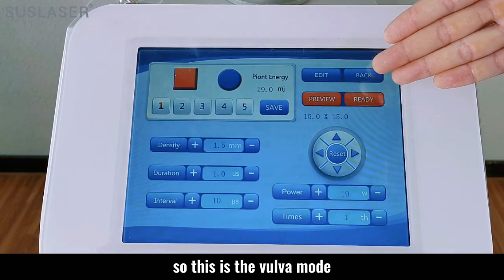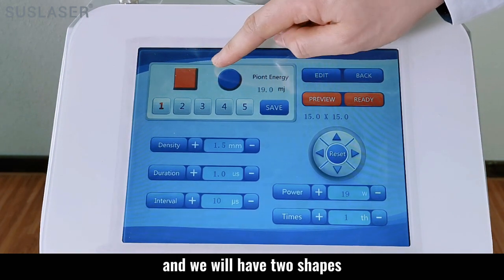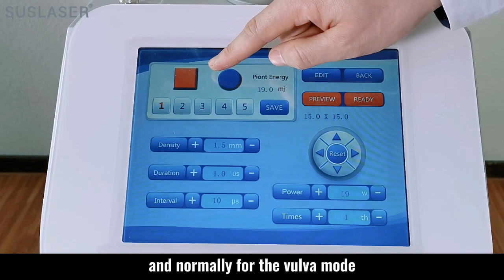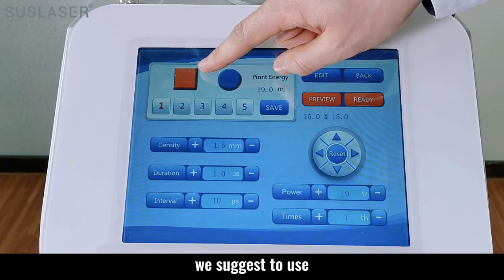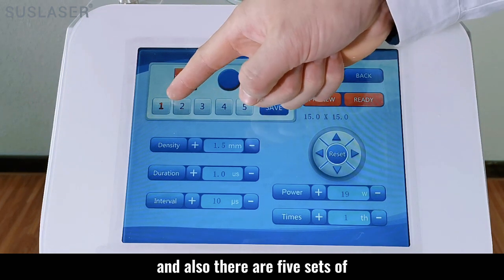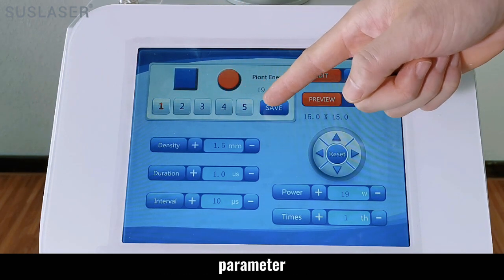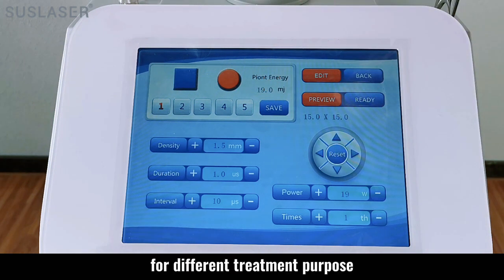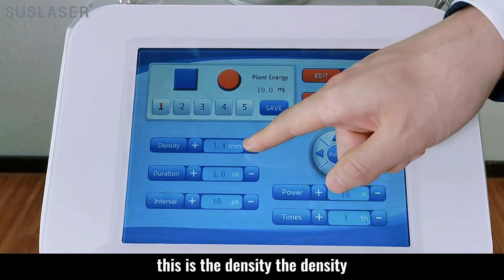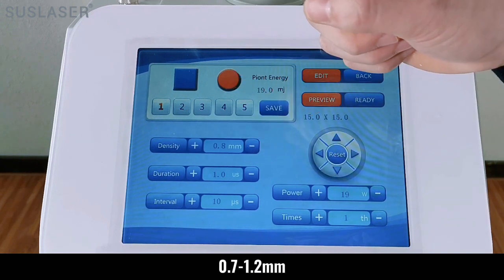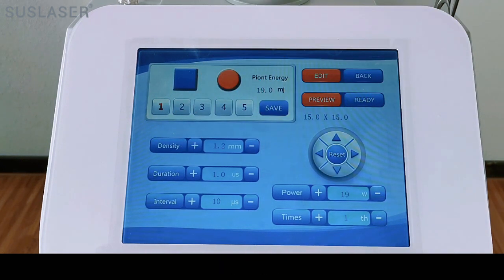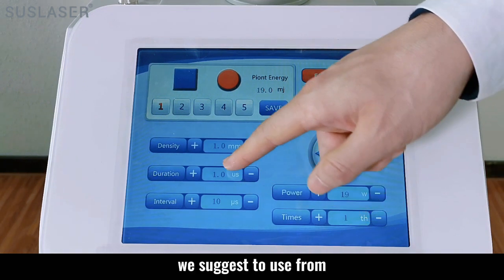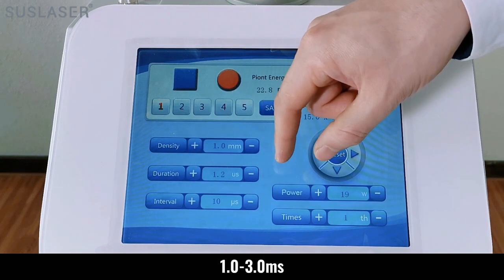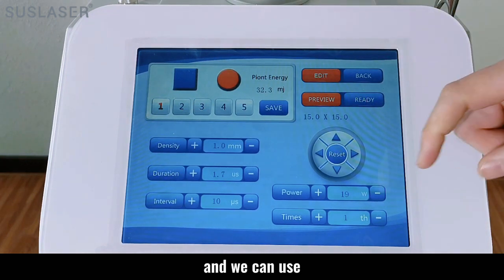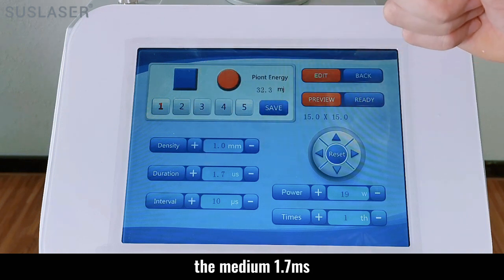So this is the vulva mode, and we will have two shapes. Normally for the vulva mode, we suggest using the square shape. And also there are 5 sets of parameter saving for different treatment purposes. This is the density. The density we can use is from 0.7 to 1.2. Normally we can use 1.0. And for the duration, we suggest using from 1.0 to 3.0, and we can use the medium one, 1.7.